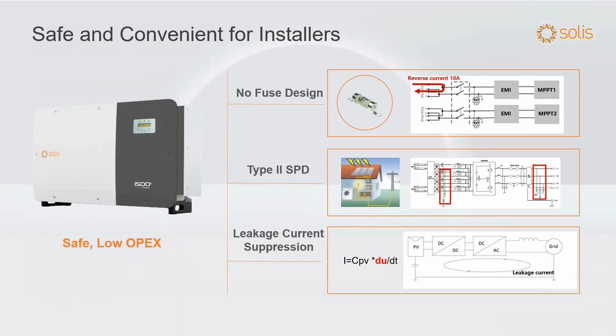All of these inverters have no fuses in them because we never put more than two in parallel at each MPPT. So there's surge protection on both the DC and AC side, leakage current suppression, as well as AFCI on all of these inverters. We call it intelligent AFCI because it can tell you what string it's on, not just what MPPT. I'll talk a little later about how you can bring 20 strings to some of these inverters.